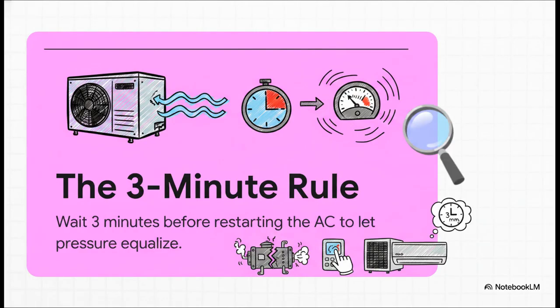This is known as the 3-minute rule. It dictates that after your AC shuts off, you must wait at least 3 full minutes before restarting it. Why? To allow the incredibly high refrigerant pressure inside the system to equalize. If you're standing there impatiently clicking your thermostat up and down trying to force it to start too soon, you are making the compressor work against immense pressure, and you literally risk destroying the whole thing. Just set the temperature, step away, and let it do its thing.